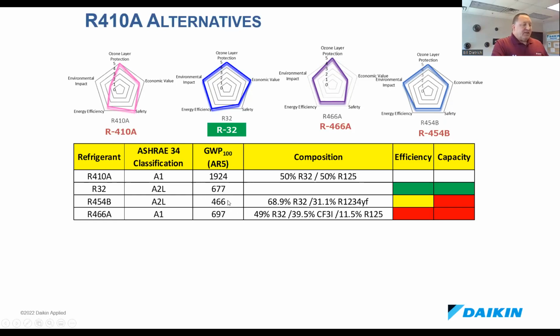R454B is the other one you'll see a lot of. Its big advantage here is its GWP is a little bit lower at 466. It's about 70% R32, and the rest is the R1234yf. Efficiency is similar to 410A. Capacity is a little bit less. And then this wild card is the 466. Whether or not this will make it as a good refrigerant, it comes in under that 750 GWP threshold.